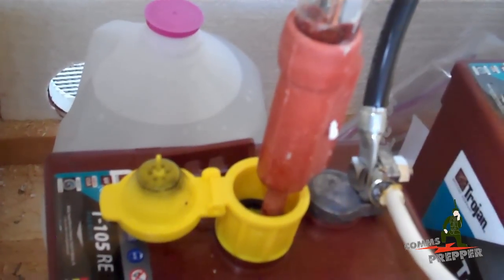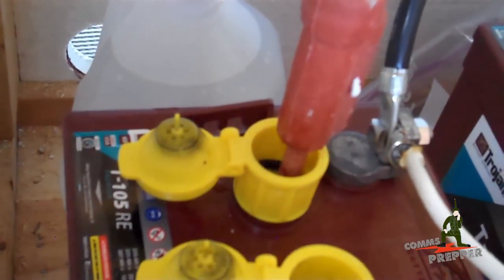As of this check, none of the cells need any extra water, so the water miser vent cap seems to be working and my battery system appears to be healthy. Again, I try to do this at least every three weeks.